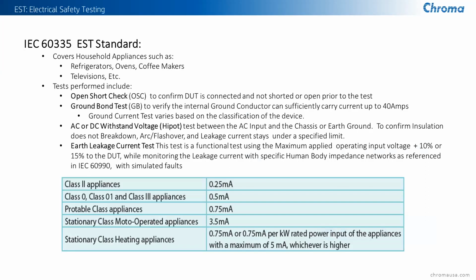The IEC 60335 covers household appliances such as refrigerators, ovens, coffee makers, and they have different classifications, and each of those classifications have different leakage current levels, ranging from 0.25 milliamps all the way up to 5 milliamps, depending on the classification of the device. It too requires ground bond, AC/DC hipot testing, and the earth leakage current test as well. The reason I'm showing these is because you're going to find that most of these do require similar testing. The level of testing and the accuracy of the measurement of the leakage current will vary based on the devices.